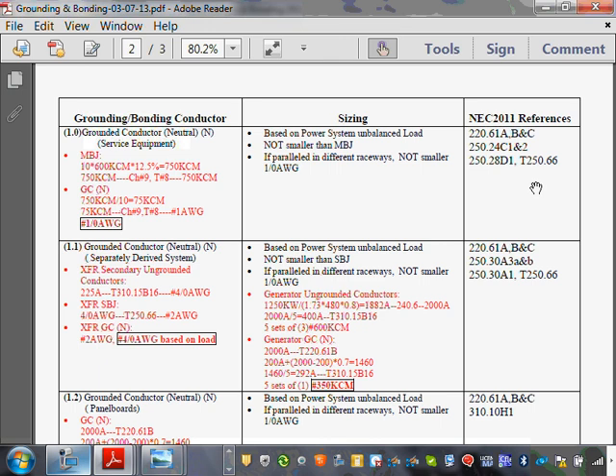If that was your 50 kW transformer, all you have to do is take the amps that you calculated here and multiply them by 1.25 for continuous load. That's all you did. At this level, like I said, at 1000 amp or higher, almost all your circuit breakers are 100% rated circuit breakers. Meaning, if you have a 1000 amp circuit breaker, you can pull 1000 amps out of it. Right now, if you have a 100 amp breaker, how much can you pull continuously, 3 hours or more? 80%, only 80 amps continuously.